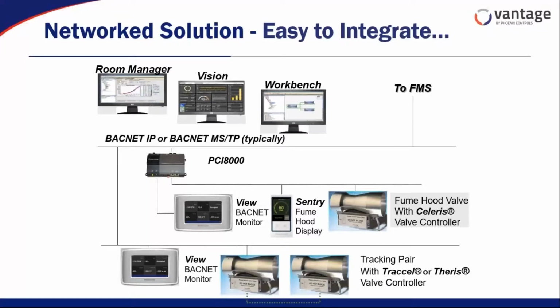gives you the analytic capability, the trending capability. It gives you some graphs to show you what your energy usage is in your space, how you can reduce your energy footprint. It's a critical front end solution, but it's not meant to replace 100% of your building automation system. So we call it the Vision Critical Environment Solution, or the Vision CE, and that gives you a look into everything in your critical environment system. It can also pull in third-party BACnet data, not just Phoenix systems. So if you had fans or some kind of a CO2 sensor, TVOC sensor inside the space where the Phoenix equipment is, all of that can be merged into one front end with the Vision software.